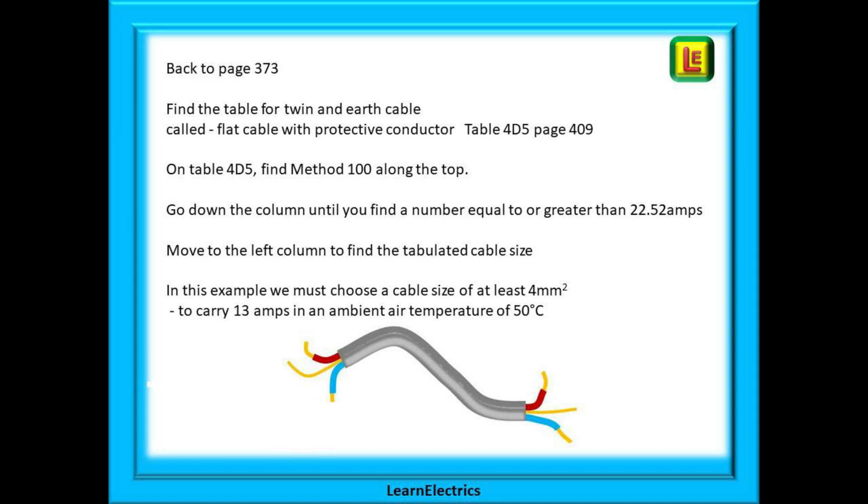On table 4D5 find method 100 along the top. Go down that column until you find a number equal to or greater than 22.52 amps which is 27 amps. Now move to the left most column to find the tabulated cable size. In this example we must choose a cable size of at least 4 millimeters to carry 13 amps in an ambient air temperature of 50 degrees centigrade.